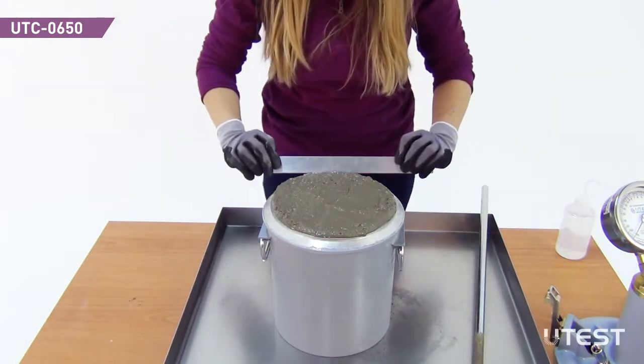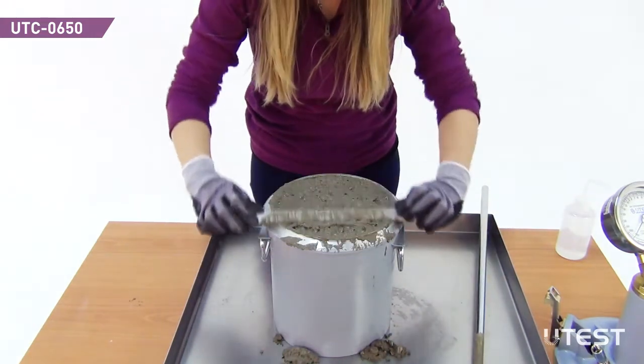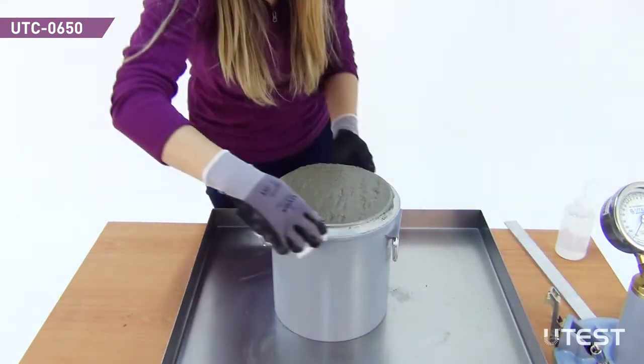Strike off the top surface by sliding the straight edge across the top rim of the measuring bowl and clean the contact surface.